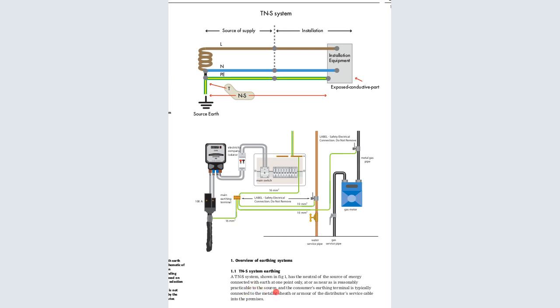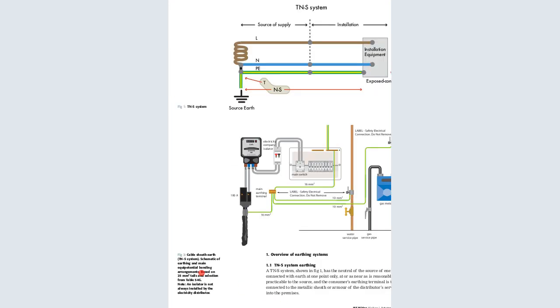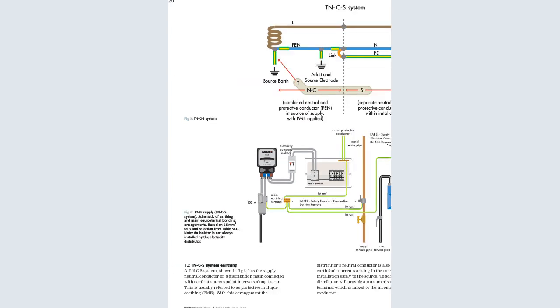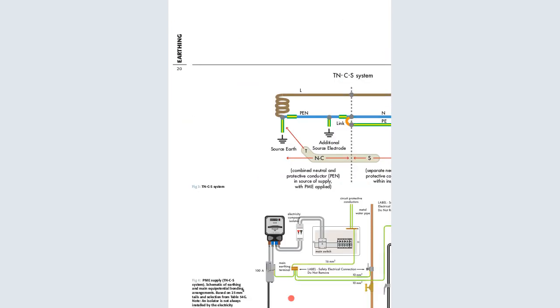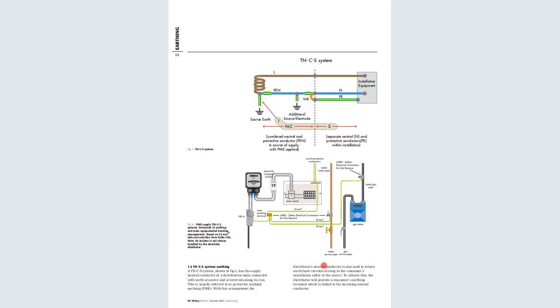practicable to the source. So the consumer's earthing terminal is typically connected to the metallic sheath or armor of the distributor's service cable to the premises. So the cable sheath earth, that is the TN-S system, the schematic for the earthing and the main equipotential bonding. It has the 25 millimeter square tail of the selection. Then when we go on, now this is another system. It is called the TN-C-S system.